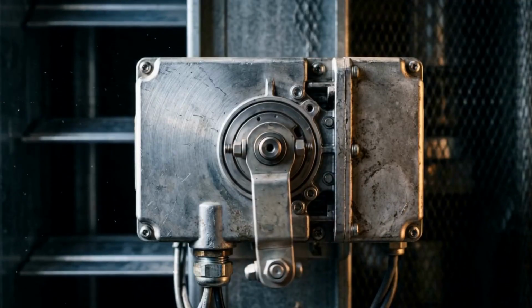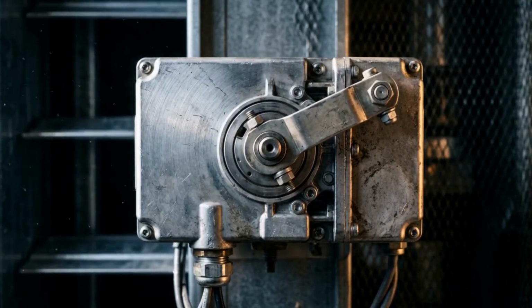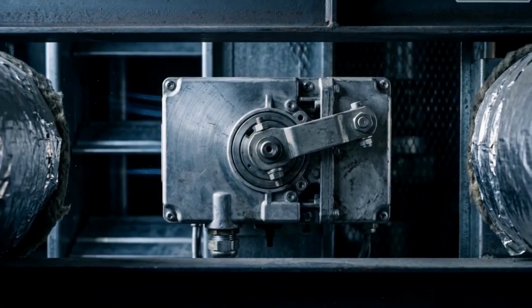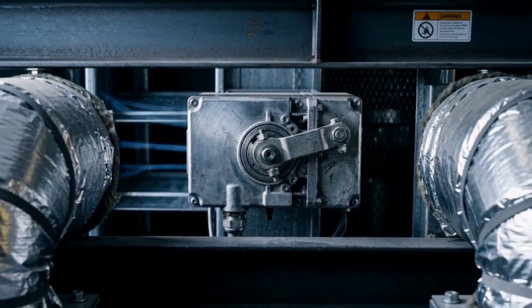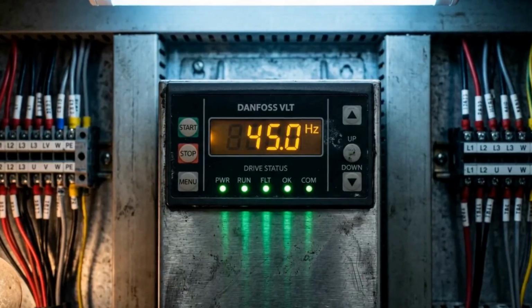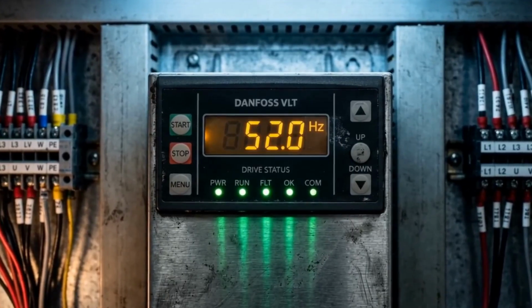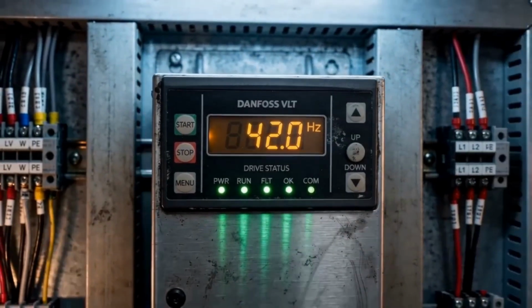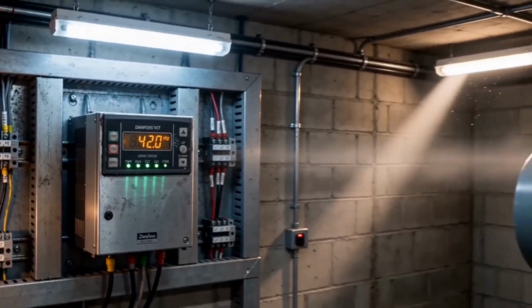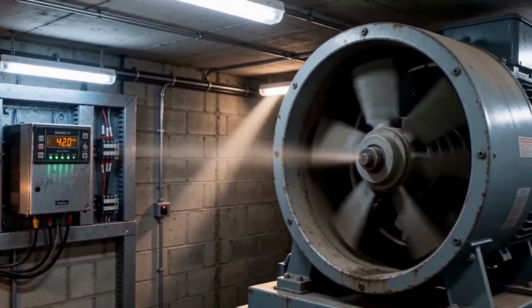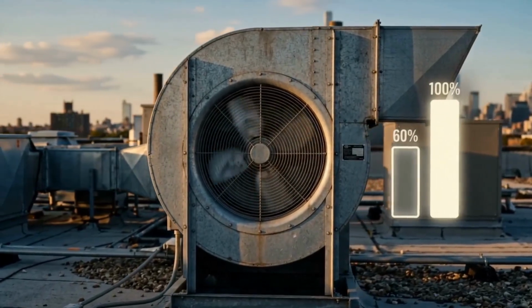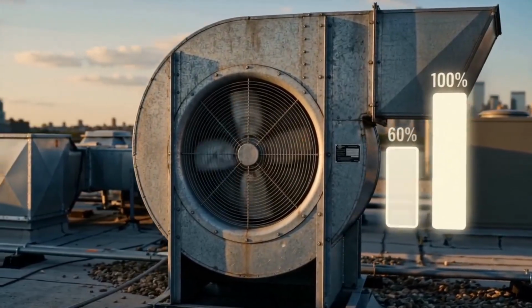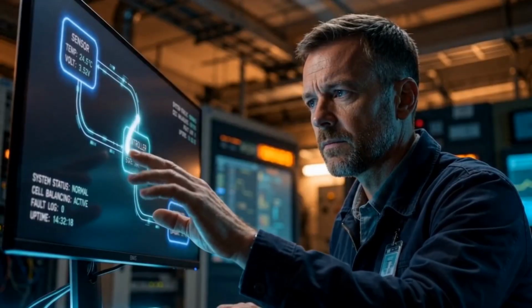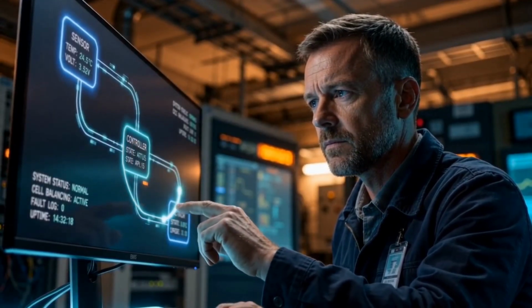Outputs are where the BMS acts. Damper actuators modulate outside and zone air. Valve actuators throttle chilled and hot water to match space loads. Variable frequency drives, VFDs, adjust fan and pump speeds so motors run at the required speed, saving significant energy compared to running at full speed. A supply fan at 60% can use far less power than at 100%. Together, these inputs and outputs form closed loops. The building reports conditions, the BMS responds, the building stabilizes, and the cycle repeats continuously.